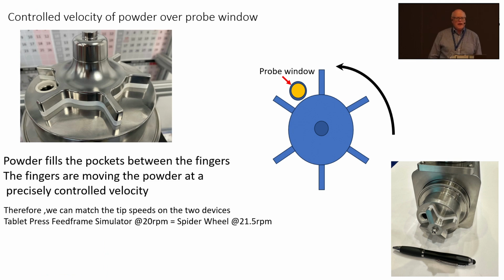In Pfizer, we did need in places to do measurements in chutes. And the way we got around the effect of segregation in terms of the flow, because of just relying on gravity, was to put this device here, this spider wheel, into the chutes, or actually into tubes. And Expo have been making these for Pfizer for quite a while, in different sizes. And you can see this is a way of taking a flowing material that's coming down a chute and capturing it with a spider wheel and making sure that the powder moves at a consistent density and a consistent velocity. So this is a way of overcoming the problem of free-fall chutes, where you can get a difference in velocity of the powder, which causes errors in the prediction of the near-infrared.